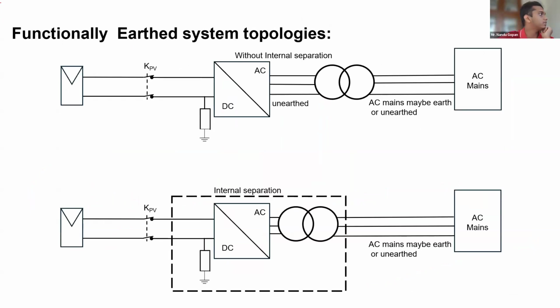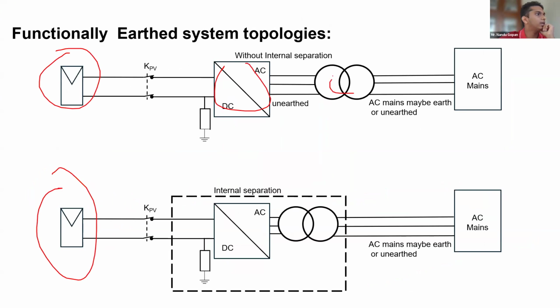So, functionally earthed system topology for a PV array. This is a PV source. There will be an inverter, and there will be a separation, an isolator, a transformer, and one of the line conductors will be earthed with an overcurrent protective device or a residual current monitoring device. So this thing which I have marked in red will either be an overcurrent protective device, which can be a fuse. According to the standard, at 0.5 kilowatt it should be a fuse of a certain rating. Or else it can be a residual current monitoring device.